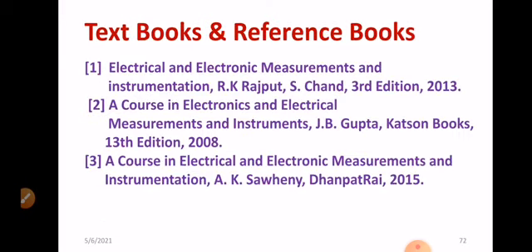I have referred to the following textbooks to gather the information. In this video, I have discussed what R.T.D means, what the constructional details of R.T.D are, how R.T.D operates, and I have shown you certain graphs. How do you measure temperature by considering the resistance value? Later on I explained how you measure the resistance by using the Wheatstone's bridge principle. For R.T.D we require a Wheatstone's bridge, and we also have to apply different compensation: 2-wire, 3-wire and 4-wire compensation. We found that 4-wire compensation is most accurate but a little bit expensive. Thereafter I explained the major advantages and disadvantages of R.T.D. Finally, I have discussed a few applications of R.T.D.